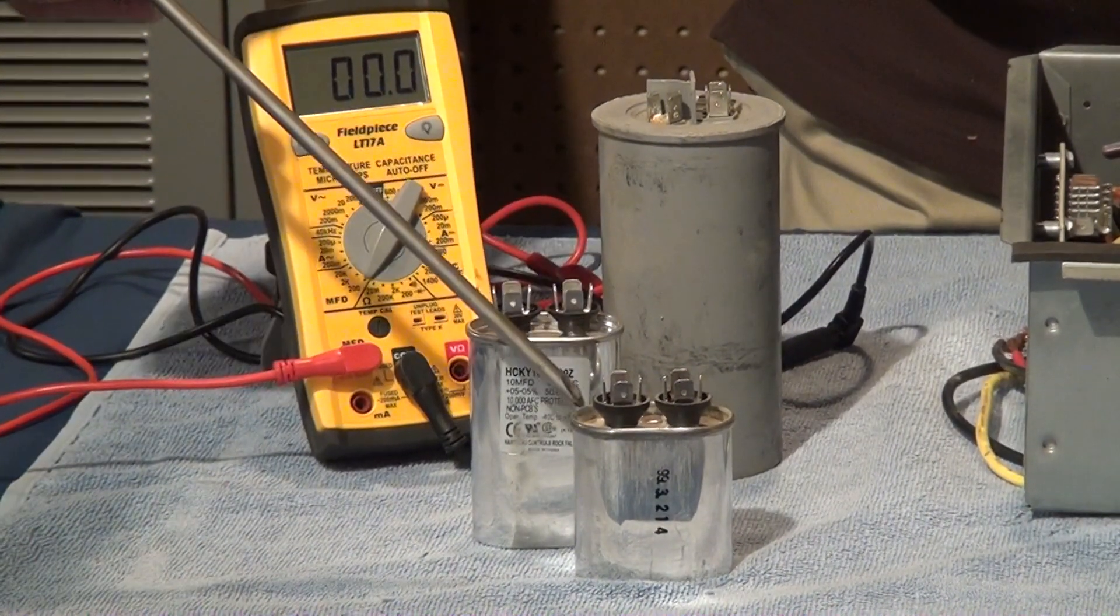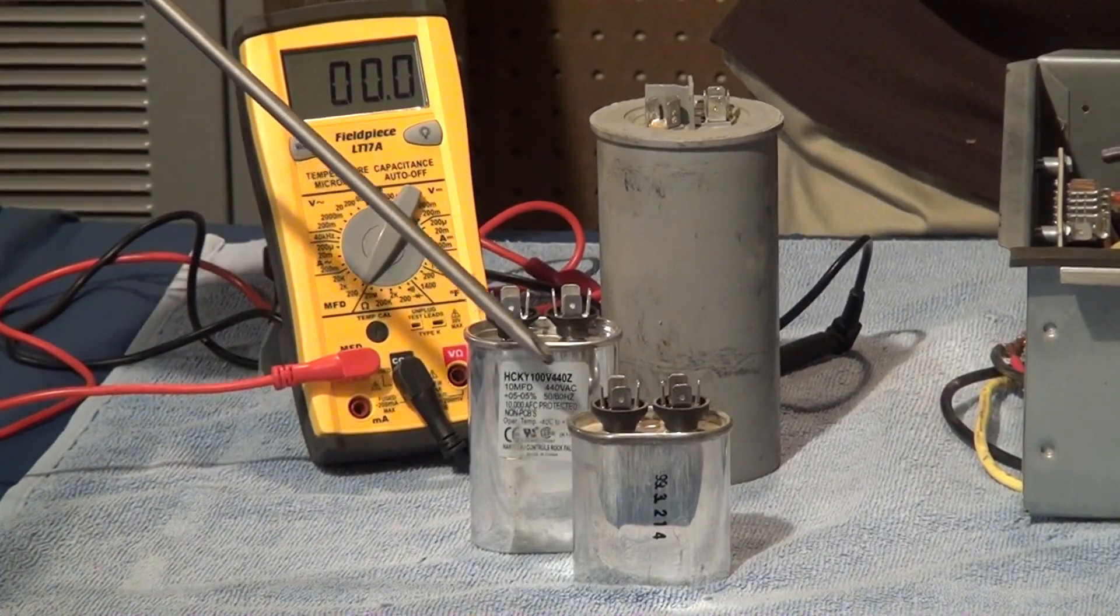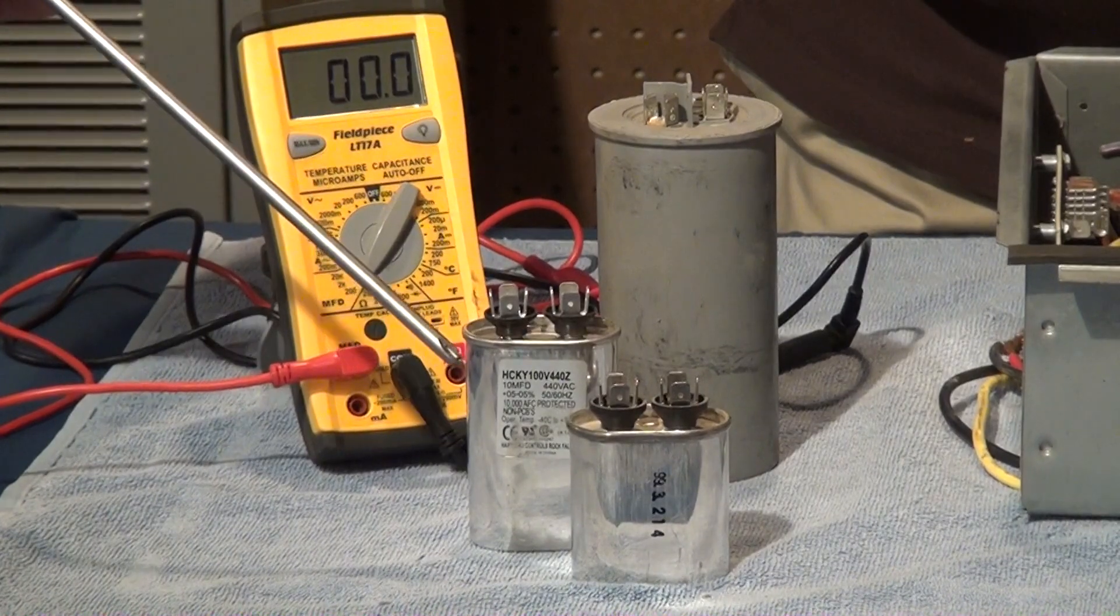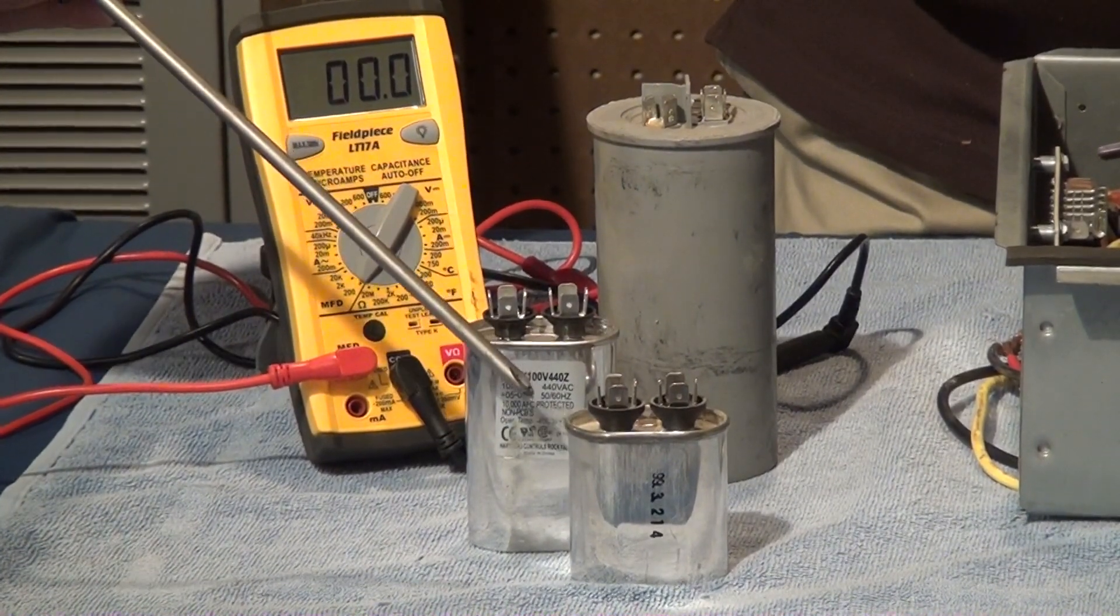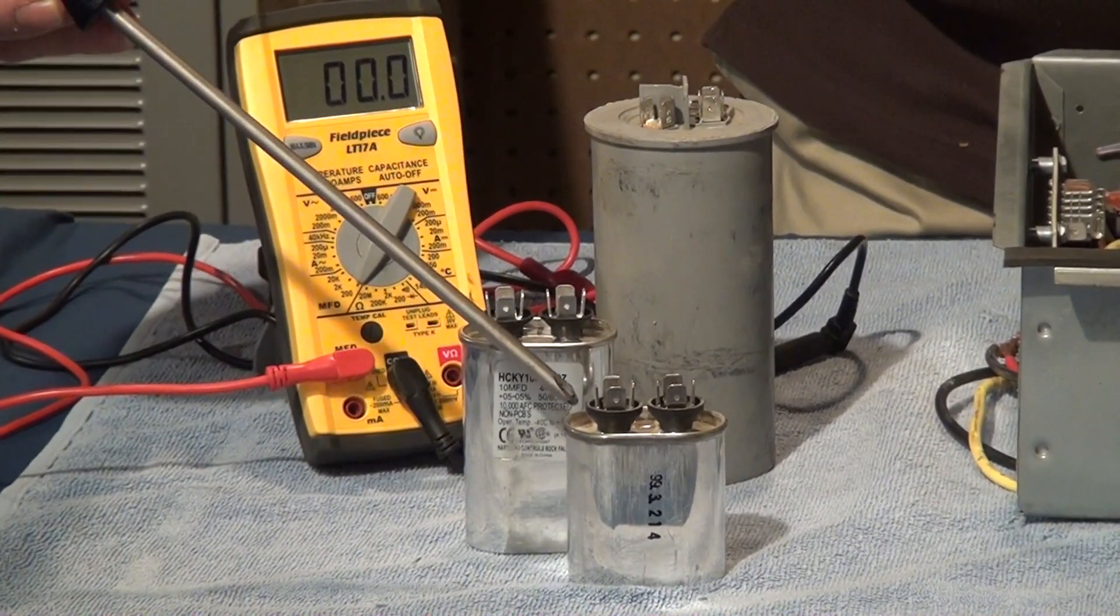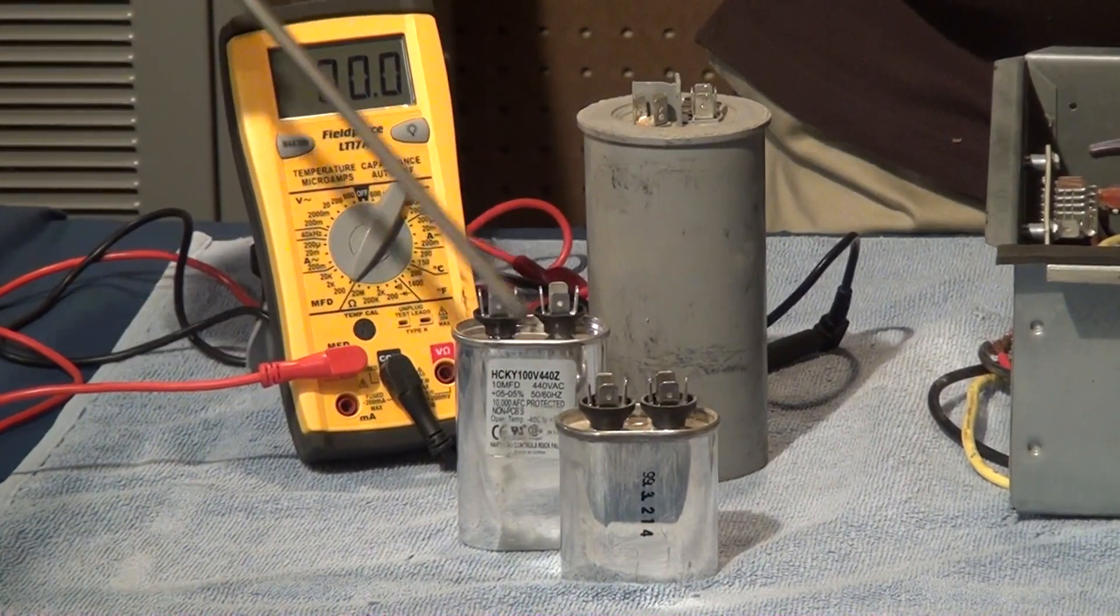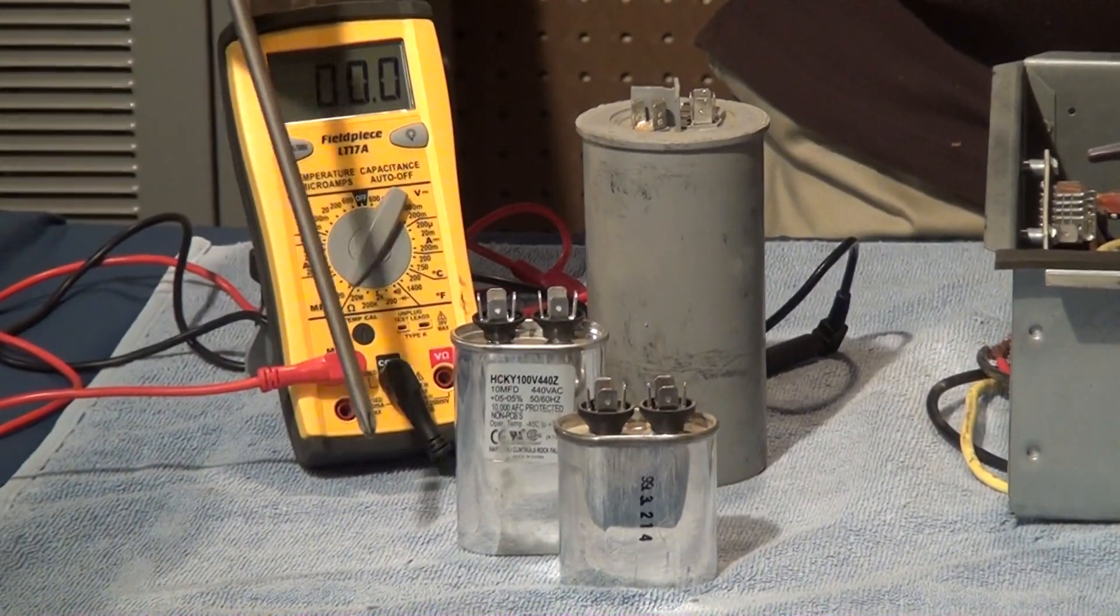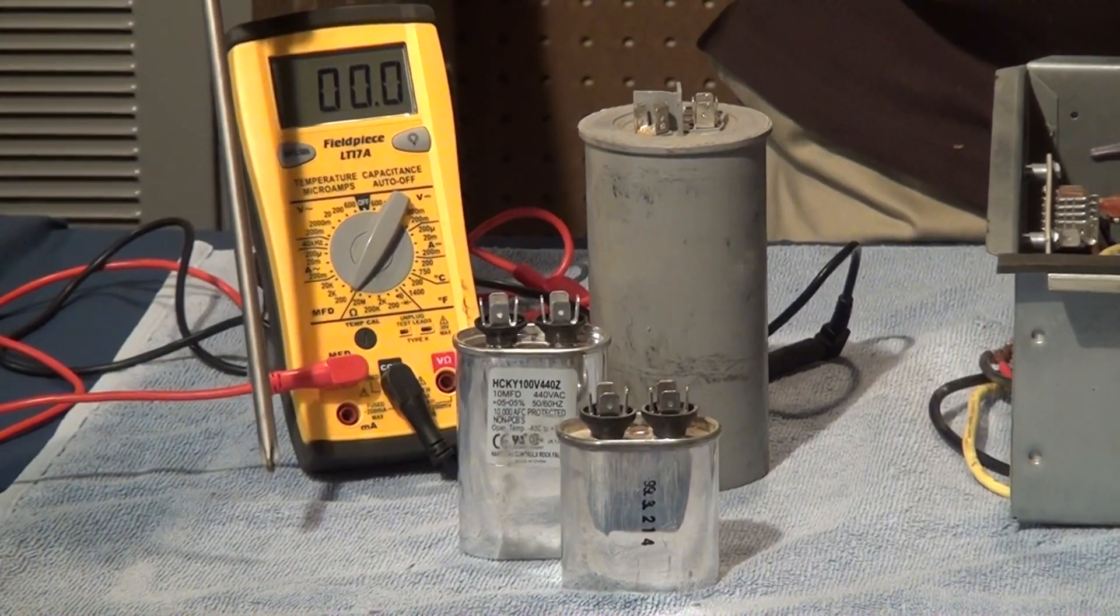We want to point out that the fact is that these two capacitors when they're wired in the circuit according to the diagram that we're showing you, they are wired in parallel. So what we would do is we would add up the total capacitance so that we would know what was exactly in that circuit going through the start winding in the run mode. Now this is one way that they would show them.